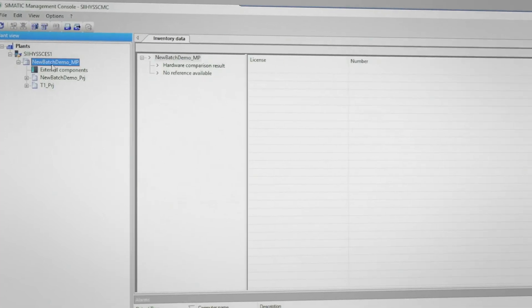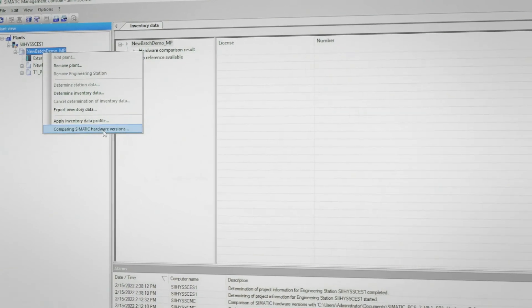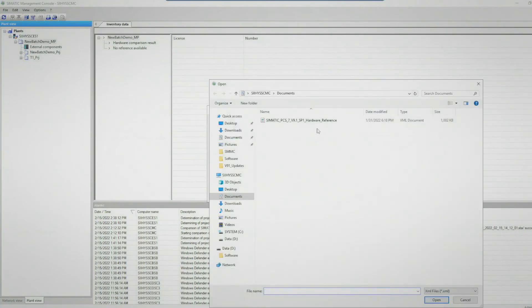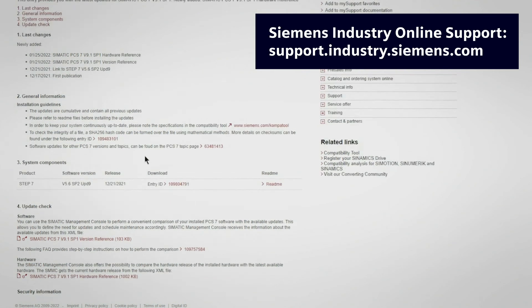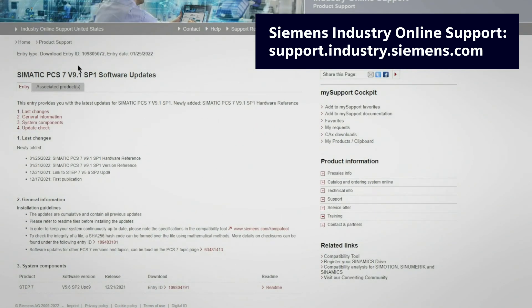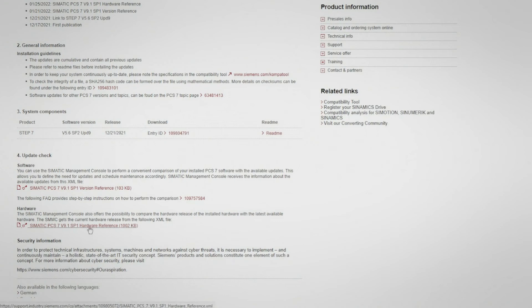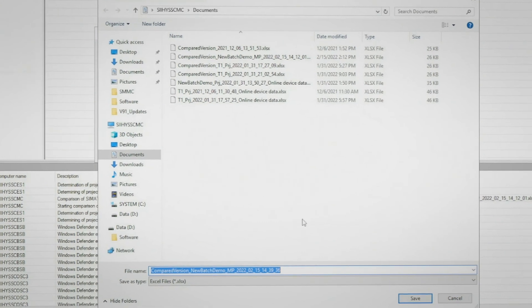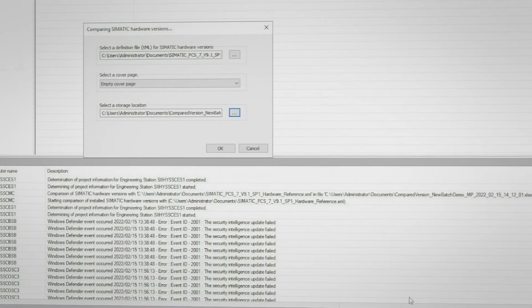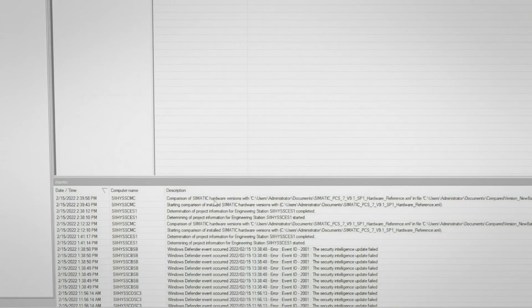When the project arrives in our plant view, we can right-click and choose Compare SIMATIC Hardware Versions. Next, we need to select the latest XML reference file. The hardware reference file can be downloaded from the PCS7 version 9.1 Service Pack 1 Software Updates page on the Siemens Industry Online Support site. We'll leave the empty cover page selected and then select the storage location for the report to be generated. After that, we can hit OK and then wait for the message that the comparison has completed successfully.